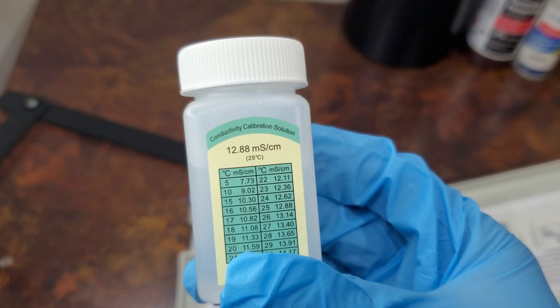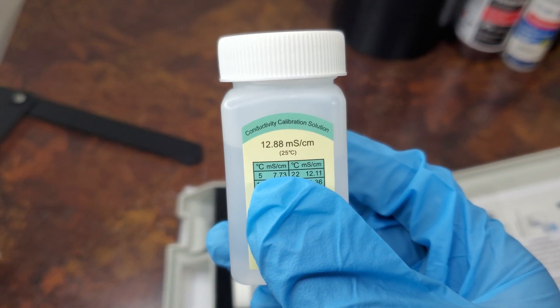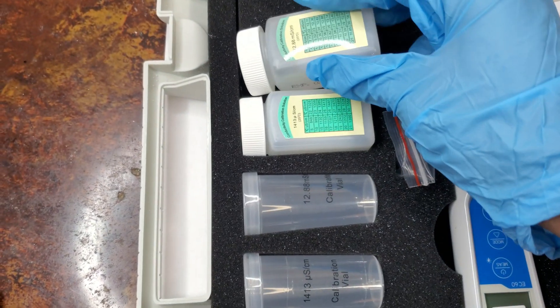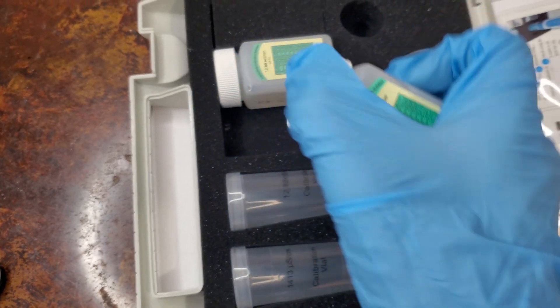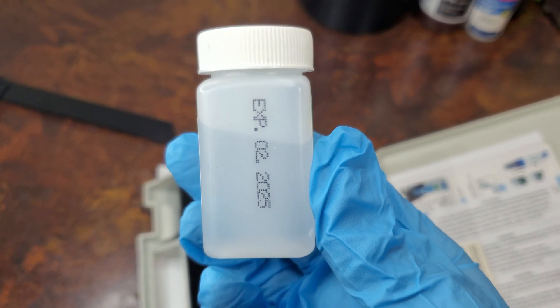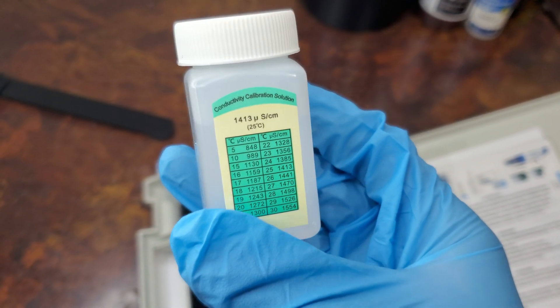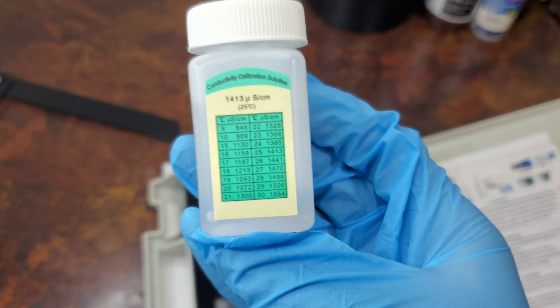Conductivity Calibration Solution of 12.88 mS/cm — this makes sure our device has a two-point calibration. Conductivity Calibration Solution of 1413 µS/cm — this makes sure the device has a one-point calibration.